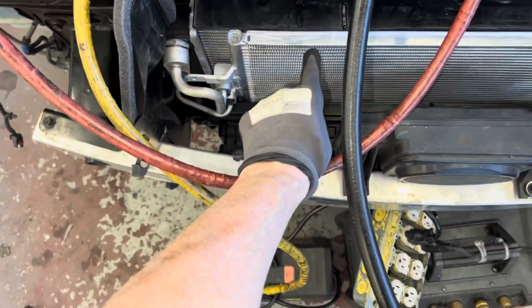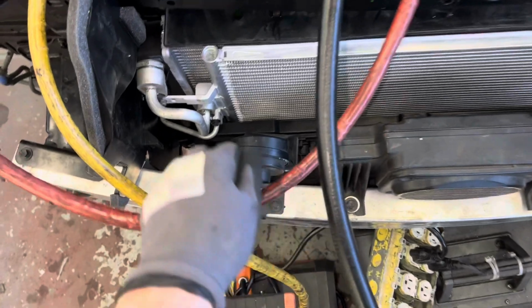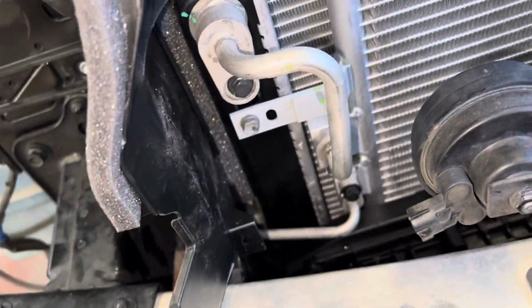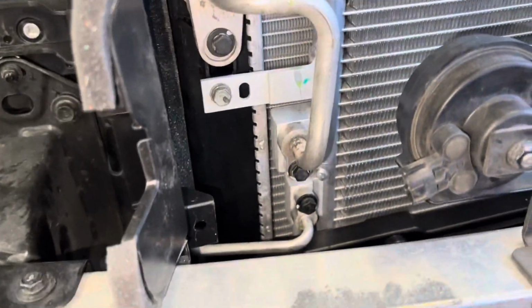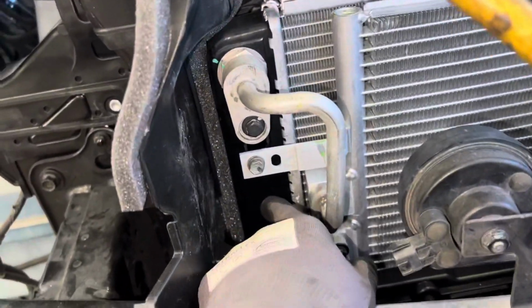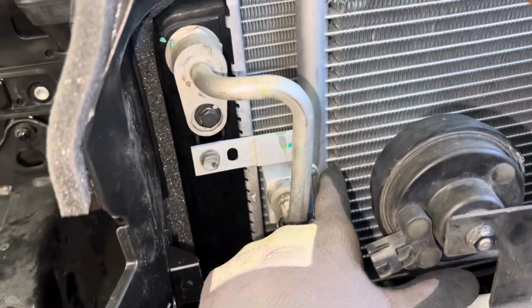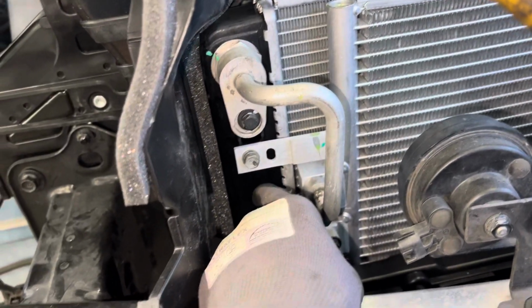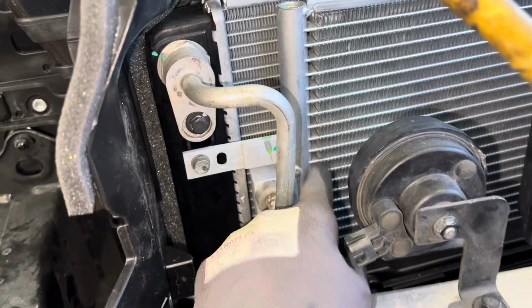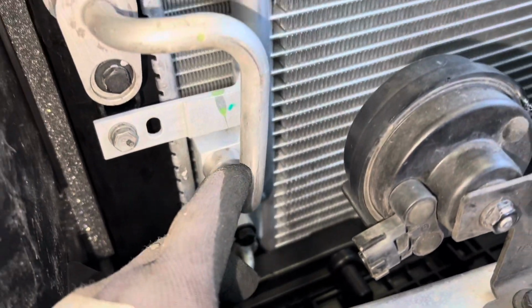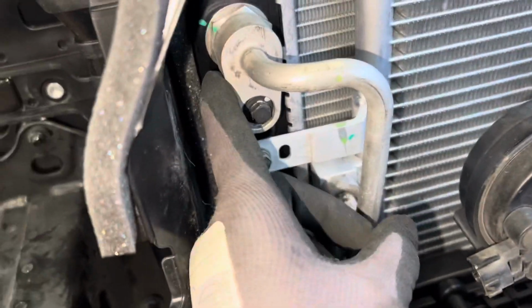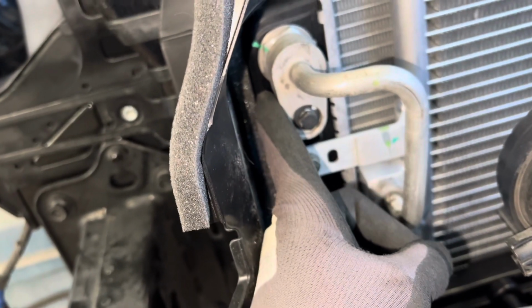But take a look down here and tell me what you see. I'm going to tell you that this is the condenser. Now take a close look at the piping. Look really close at the piping. Where is it going? You see something a little different, a little odd there? Oh, what's that right there? What's this, a glycol heat exchanger? What's this, a refrigerant condenser? We got two heat exchangers, a glycol heat exchanger and a refrigerant heat exchanger, but yet, look at the piping. It comes out of the refrigerant heat exchanger into the glycol heat exchanger. It doesn't go back to a compressor immediately.